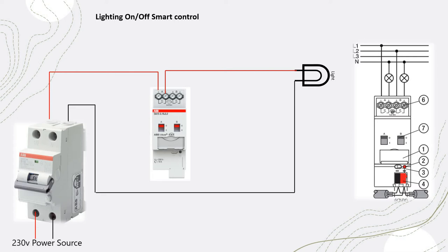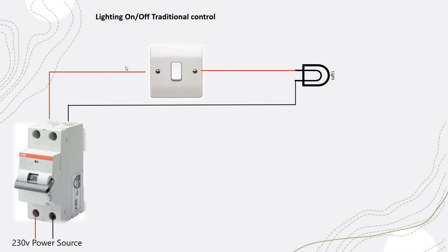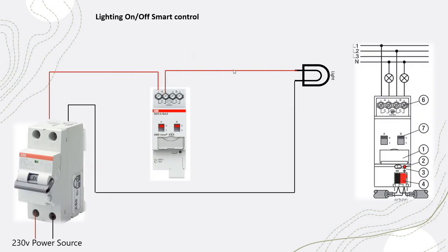The question is: where did the switch go? The switch is looped through the KNX port and has nothing to do with the electrical part or electrical connectivity. It connects through the KNX port from the electrical DB to the room, and the switch communicates smartly with the actuators and all devices in the system. Compared to conventional wiring where live voltage runs inside the wall, here you only have a keypad on the wall connected via KNX bus cable, which is DC voltage — much safer.